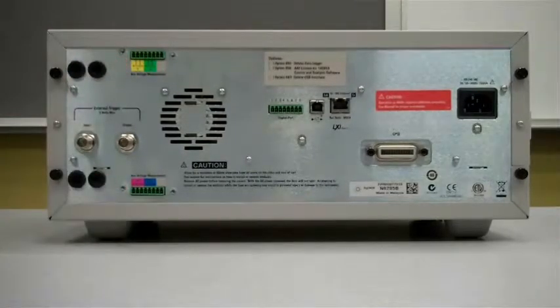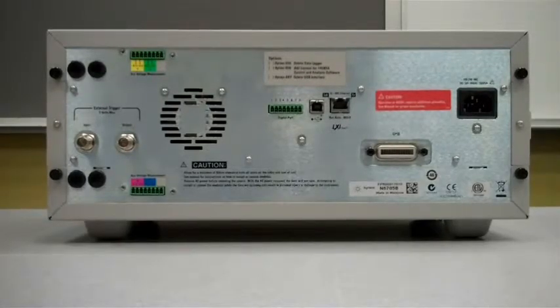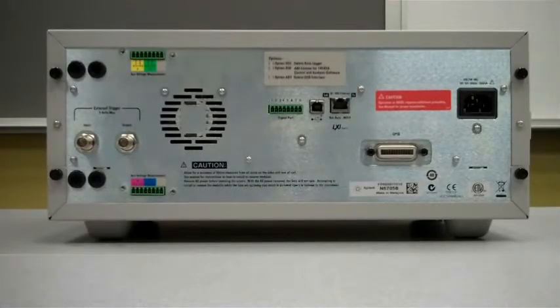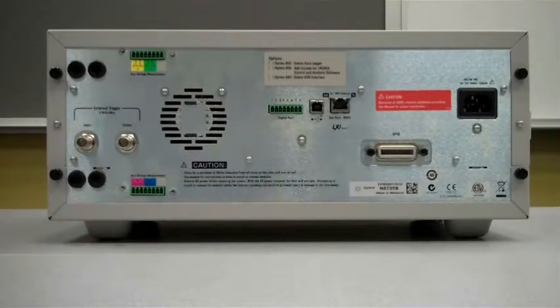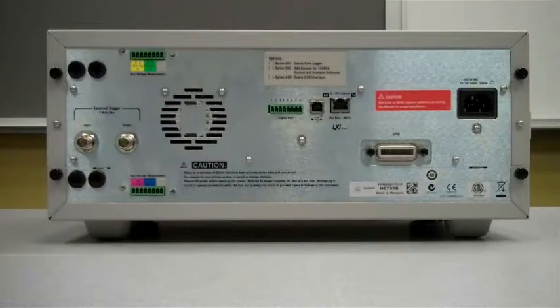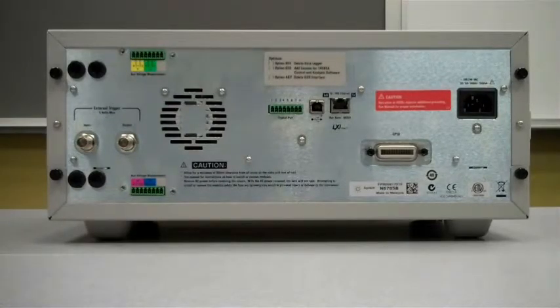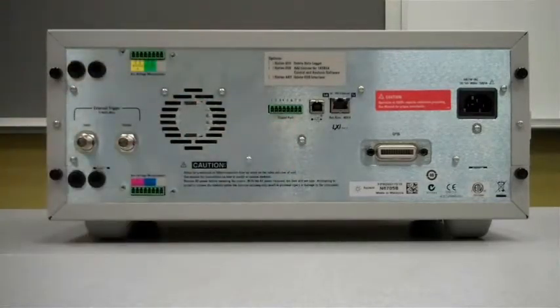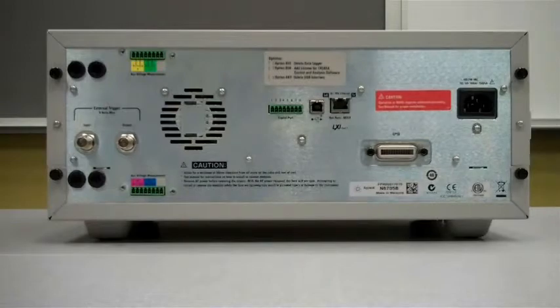There's also these two connectors here for the auxiliary voltage measurement on the N6781A module. On the inside, you plug the connector in and then that'll break those out to the rear panel so that you can access them with the covers on. All these connectors, the 8-pin connectors you need, are included with the mainframe in the box that ships.